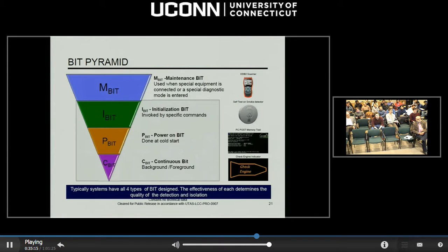That's P-BIT. Then C-BIT is the stuff that I do under normal operation that is done in the background typically. These are limit checks, these are rate checks, these are background RAM checks in computers. But these are things that are using the signals and my inherent knowledge of those signals to say they're good, they're bad, or I don't know. This is where a lot of the problem occurs, because when I'm looking at some signals in terms of their validity, it's in range, it's out of range, it's moving too fast, it's moving too slow.